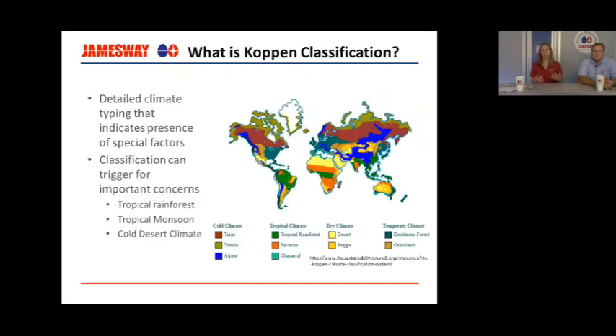So from that, one of the things we can use is the Köppen classification. This is a very detailed climate typing, so it looks at not only the maxes and the mins of the temperature and humidity, but it also looks at other factors that occur. And this classification can trigger us in the HVAC world for some important concerns. So if the classification was a tropical rainforest, a tropical monsoon, those would be customers that you definitely need dehumidification. If you get the cold desert climate, that's the prairies, right? It's incredibly cold and incredibly dry. So these give us very quick tips, and the Köppen classification is on Wikipedia for most major cities, minor cities, and most townships around the world. So you can find that as a very quick trigger as to what special conditions are happening there.